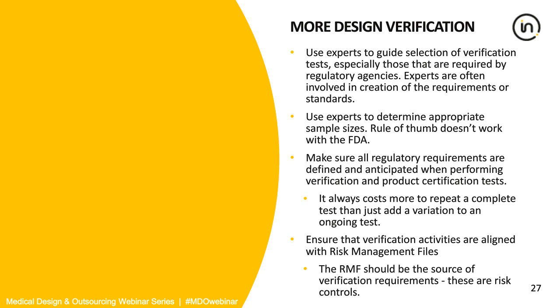Make sure all your regulatory requirements are defined and anticipated when performing verification and product cert tests. What I mean there is if you think you're going to go into 4 different countries and each country has a slightly different voltage requirement, make sure that you've got that all defined as you go in, and when you ask to have that testing performed, make sure that it's done at that one time. Because if you go in there and just say, okay, test me to the U.S. voltage requirements, and then you come back and say, I want to go to Korea, and we say, well, you're going to have to retest it, it costs a lot more money to go in the lab twice than once.